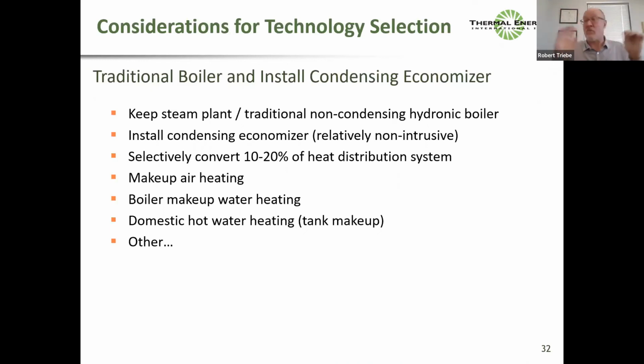And of course, heat recovery is what I've been doing my whole life, optimizing large systems. This is something that is commonly done, but I don't see it out in the field. So, instead of looking at a hydronic system and a plant and a facility as one big heat sink, think about the different heat sinks and how you can stage and apply your heating with pinch principle to get the highest efficiency, rather than just blending all the 180 and 160 and 140 sinks together and trying to hit them with one big hydronic loop. You're missing a huge opportunity.